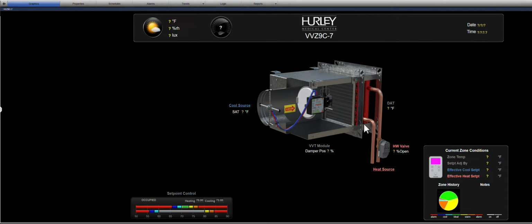Let's take a look at where we're at with this to see if we can find out anything to improve this chronic orange and yellow condition that we see. Over the past 2 or 3 weeks, I've seen this area orange a lot. We're looking at a supply temperature of 52.3 degrees coming from the cool source, which is air handler 2. This week we commissioned air handler 2, so we know this is live data from that particular supply sensor on that air handler. Over here, we've got about 53.2 discharge air temperature.